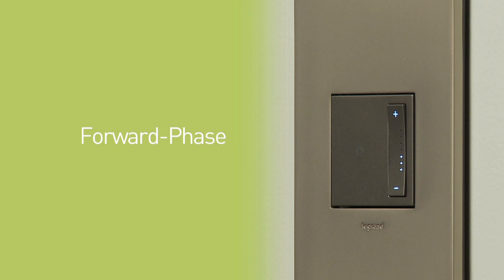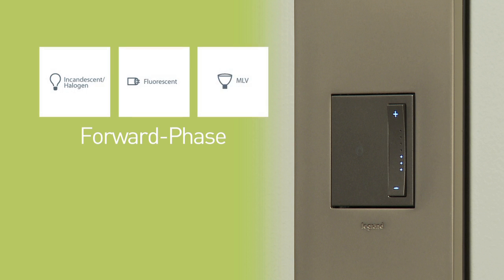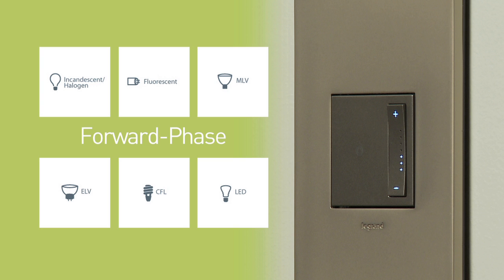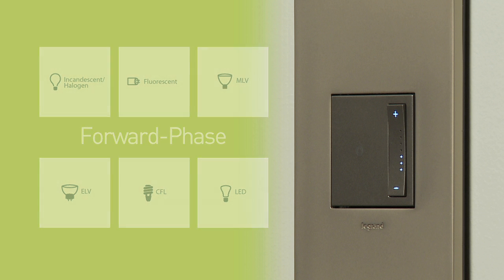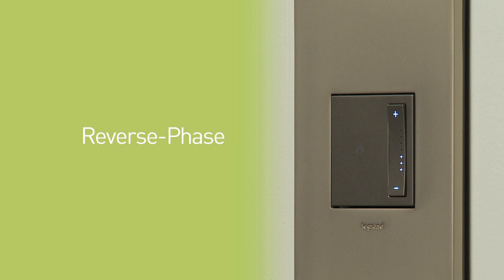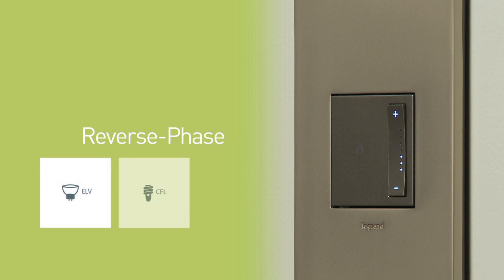Your dimmer's default setting supports forward phase loads such as incandescent halogen, fluorescent, magnetic low voltage, forward phase electronic low voltage, and most CFL and LED bulbs. However, you can modify this setting and adjust it to support reverse phase loads. This includes reverse phase electronic low voltage as well as CFL or LED bulbs that specify reverse phase dimming on the packaging.